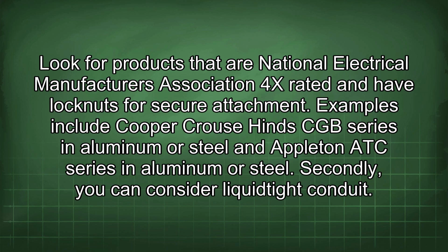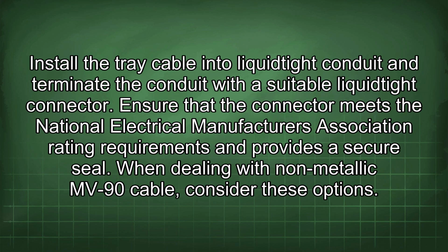Secondly, you can consider liquid-tight conduit. Install the tray cable into liquid-tight conduit and terminate the conduit with a suitable liquid-tight connector. Ensure that the connector meets the National Electrical Manufacturers Association rating requirements and provides a secure seal.